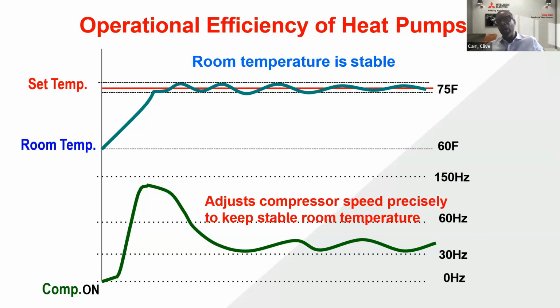Now, with the inverter technology, because the operation is continuous, it balances out the temperature in the home. One of the reasons we ended up with a 4 to 5 degree temperature difference between the downstairs and the master bedroom upstairs is the traditional system operation, in that it comes on at its full capacity and tries to attain the set temperature. The thermostat is in the main living area, so once that zone has been satisfied, the system is turned off. The other zones throughout the home have not reached the desired temperature, but the location of the thermostat has. So you get that swing, or that temperature difference throughout your home, because your traditional system has stopped working.